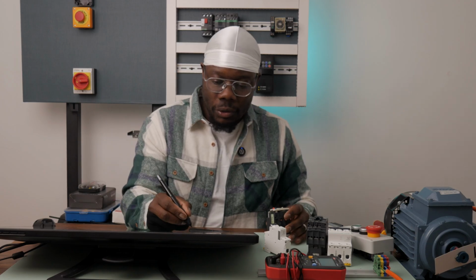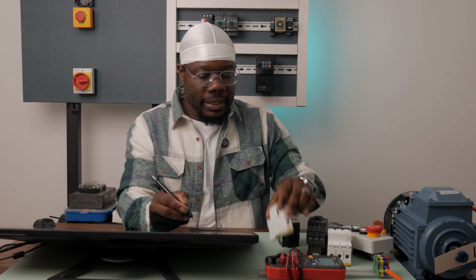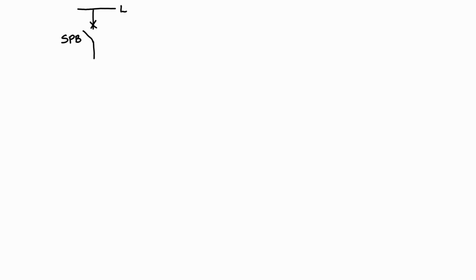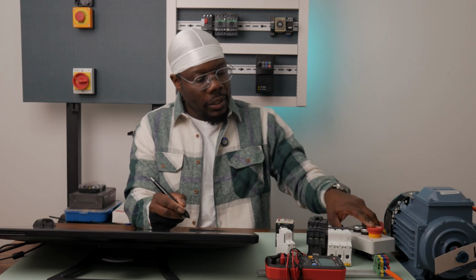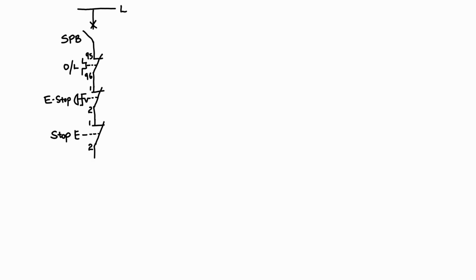And then from the control circuit breaker, you go to your 95 and 96 on your overload. My control circuit breaker here is a 6 amp single pole breaker. I'll just label it SPB, and then I'll go to my overload, which is 95 and 96. And then from the overload, let's go to the emergency stop, which is labeled 1 and 2, mushroom head, latching contact, twist to release. So this is your e-stop. From the e-stop, we go to your stop button. It's got a normally closed contact at the back, 1 and 2. From your stop push button, we go on to the start push button, which is labeled 3 and 4.